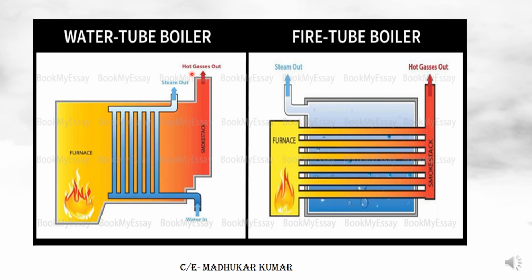Water tube boilers, basically on board ship, we have on tankers where the demand is low and high for the COPTs, and the pressure is approximately 16 to 22, 25 bar. But the fire tube boiler is utilized for bulk carriers. Sometimes you will see it on containers also. So this is for the low and medium pressure part. In shipping, it is approximately 5 bar to 10, 12 bar. That's it. So the purpose of the fire tube boiler in the shipping field is limited up to this. In another slide we will see further how things go on.